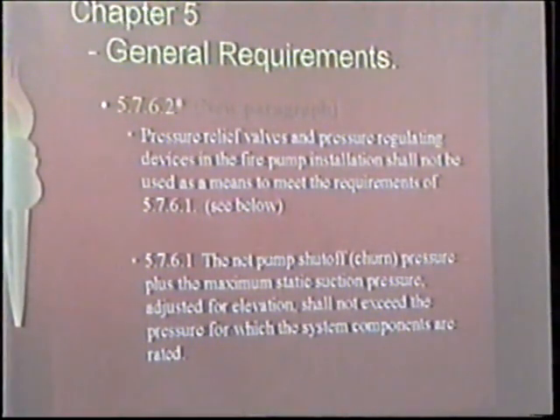So I don't know if you split hairs with them, if that means you can take the valve and move it to the other side of the thing. I'm sure that's not what they want, but I'm sure we'll see that. And one of the questions I've had in the past is system components. I mean, how far does that carry out? Is the system components just the components that they're talking about in your discharge valve assembly for the pump? Or does that mean that you're all the way up to the sprinkler heads in the system? So if that was the case, you could never have anything over 175 for most heads.